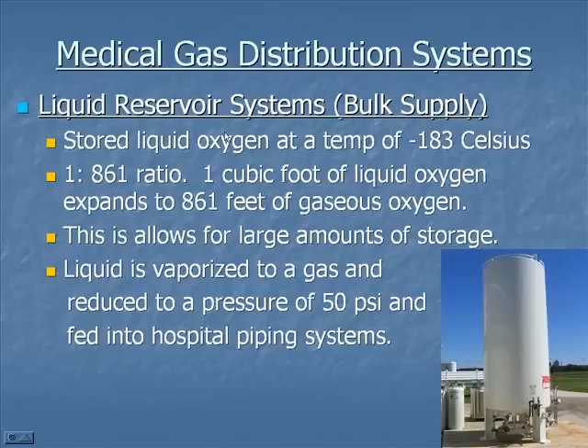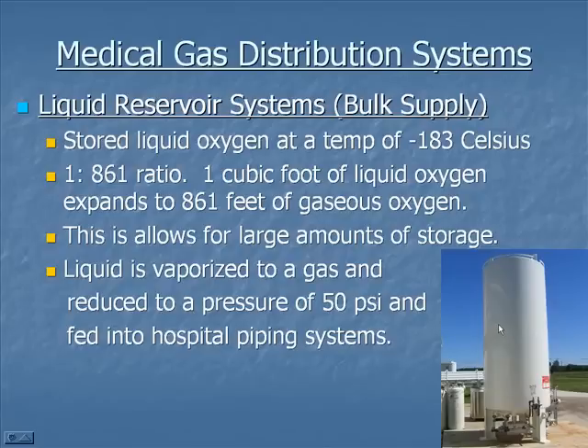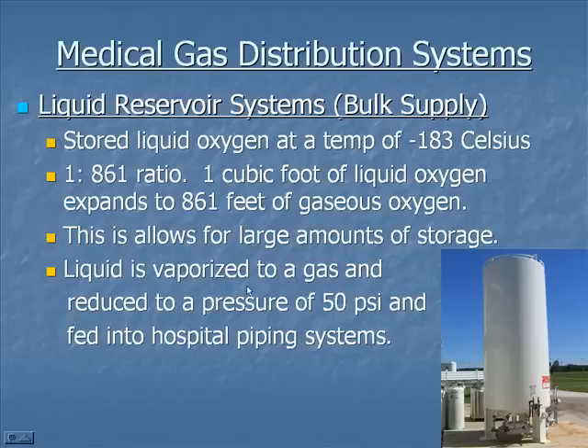Some trivia-type questions related to liquid oxygen: it's stored at negative 183 degrees Celsius. It has a 1 to 861 ratio — one cubic foot of liquid oxygen expands to 861 cubic feet of gaseous oxygen. That's an advantage because you're able to store a lot of liquid oxygen, which will then expand to an extremely large quantity of gaseous oxygen, as compared to storing oxygen in a tank where you don't have a large reserve.